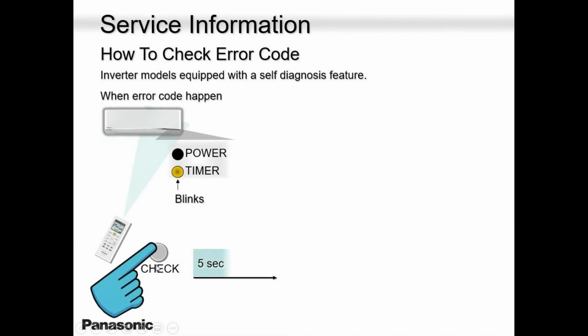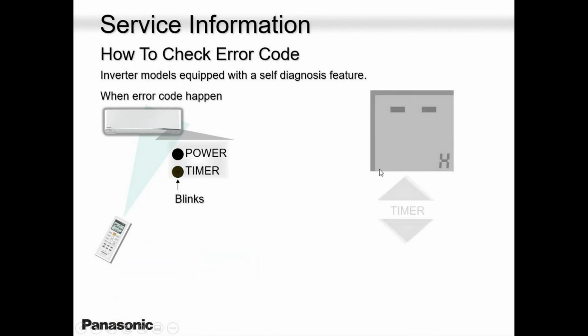So how do we do this? So you will see the timer light flashing. Okay, guys, not the power light. When the power light flashes, that means the unit is in defrost cycle. So there is a difference between power and timer. Okay, when the power light flashes, the unit is in defrost. When the timer light flashes, the unit has a problem. So please remember to tell this to the homeowner.